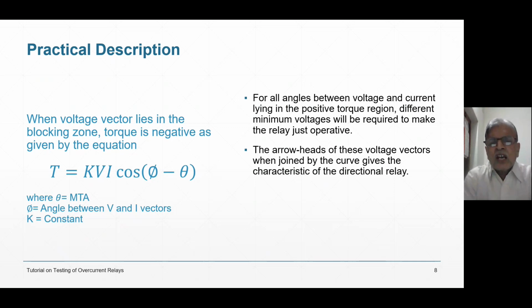Theta equal to 0 is not desired, because theta is never 0. I want the directional relay to operate when the angle between voltage and current is about 85 degrees. Therefore, I need theta 75 or 85 degrees. Usually I am using a 90 degree connection. If it is 90 degrees and phi is 75, 90 minus 75 is 15. Cos 15 is something like 96%. I am getting 96% of torque. Well, quite good. No problem.